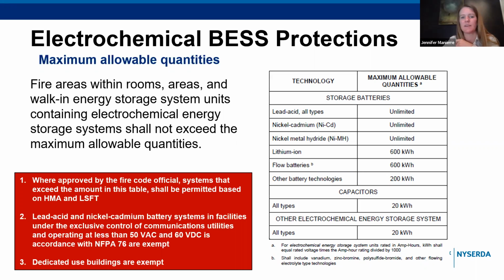Number 2 is that lead acid communications utilities exemption. They don't have the maximum allowable quantities. And then finally, dedicated use buildings are also exempt by default from the maximum allowable quantities cap. And that's just because those are buildings that have nothing but batteries in them. They don't have people living in apartments on another floor or people working in an office building on another floor. It's just batteries. The risk to human safety in those cases is very low. So dedicated use buildings don't have that requirement.